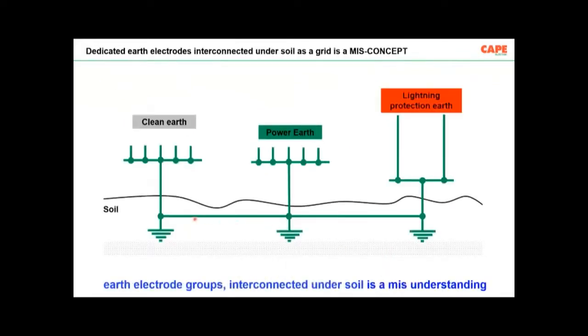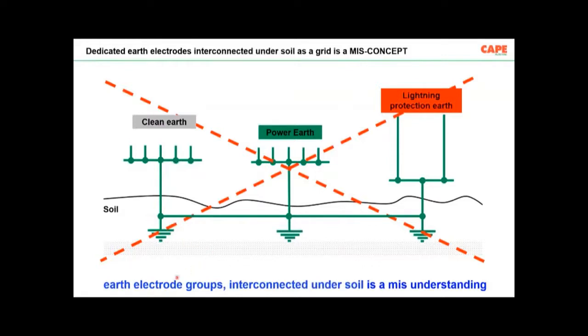And if you have different earthing, and if you interconnect all the earth electrodes under the soil as a ring or a grid or whatever, this is also wrong. You will not be able to get safety. So earthing must be done as per the picture which I have shown in one of my last slides. The exposed and extraneous conductive parts of the installation must be connected to the main earthing terminal of that particular installation through different conductors called protective earthing conductor, protective bonding conductor, supplementary bonding conductor, and so on. The impedance of these wires, the continuity resistance of these wires, are extremely important.